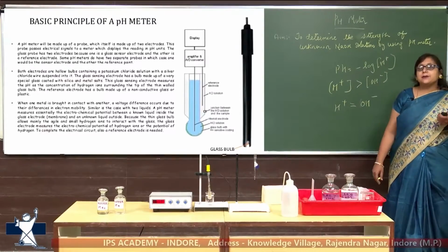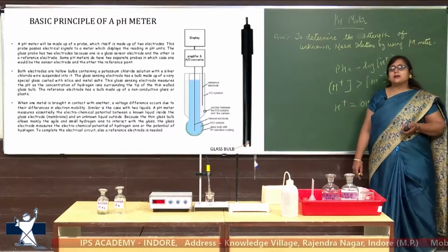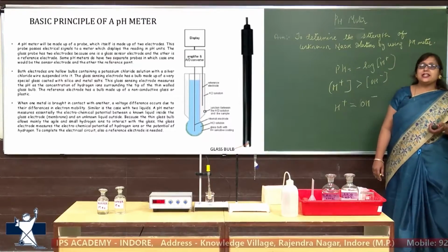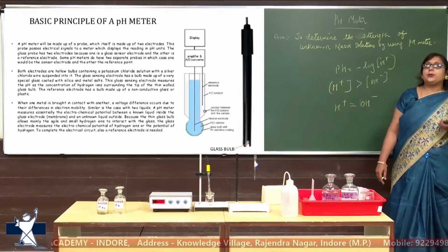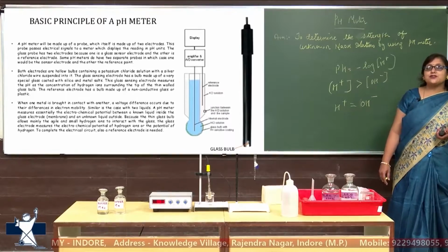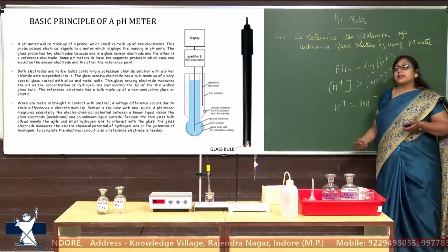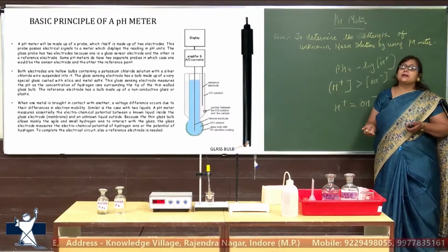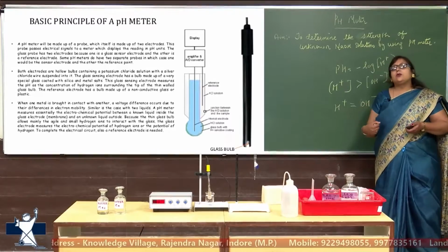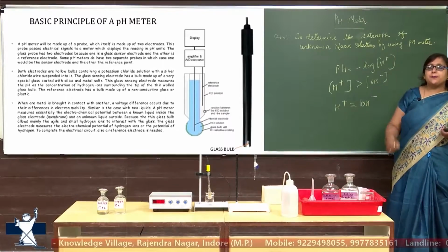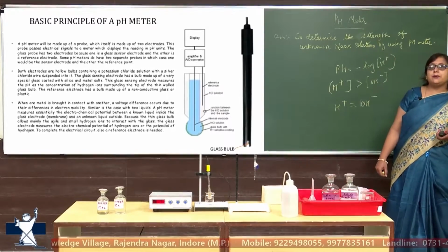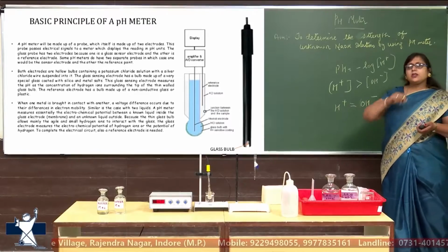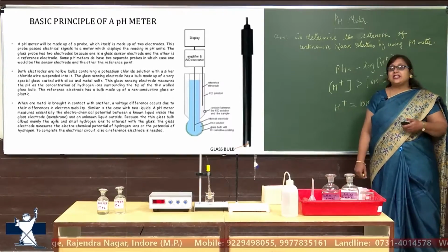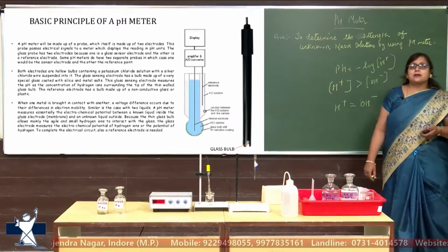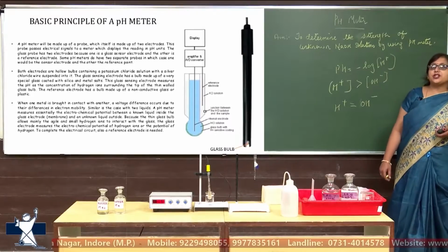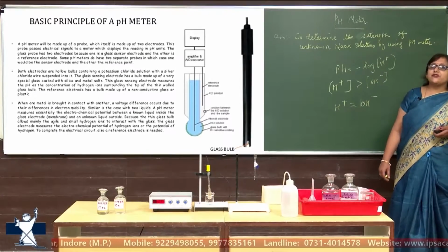different mobility. Similarly, in the case of two liquids, a pH meter measures essentially the electrochemical potential between a known liquid inside the glass electrode and the unknown liquid outside. One KCl liquid is present inside the electrode and one unknown liquid is outside the electrode, and because of this the thin glass bulb allows mainly the small hydrogen ions to interact with the glass. So, the glass electrode measures the electrochemical potential of the hydrogen ion.